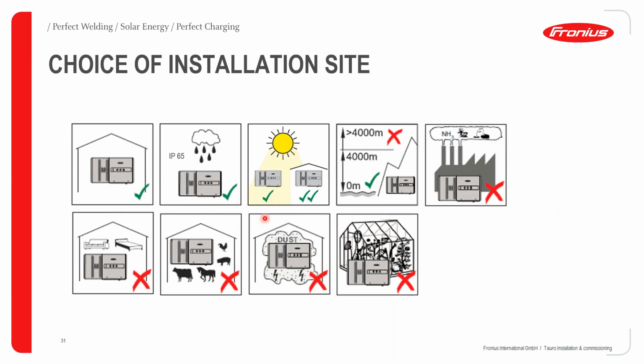The 5 then stands for protected against water jets from any angle. So what that means in a nutshell is that you can install this Tauro outdoors, and it will still operate even when it's raining directly on the Tauro itself. Obviously this does not mean you can install the Tauro underwater. That's not possible. But what is possible, as I said earlier on, is installing it outdoors. So any of these first 3 combinations are perfectly fine.